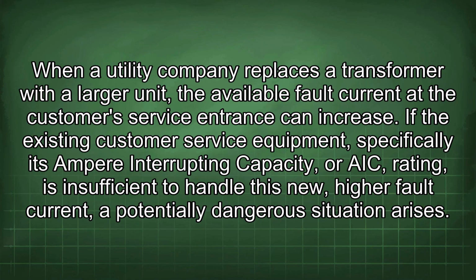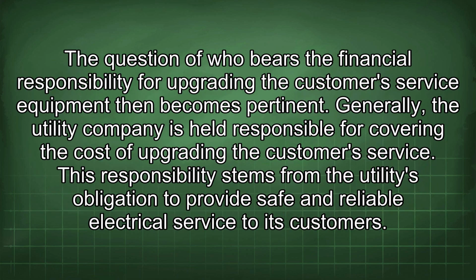When a utility company replaces a transformer with a larger unit, the available fault current at the customer's service entrance can increase. If the existing customer service equipment, specifically its ampere interrupting capacity or AIC rating, is insufficient to handle this new higher fault current, a potentially dangerous situation arises. The question of who bears the financial responsibility for upgrading the customer's service equipment then becomes pertinent.